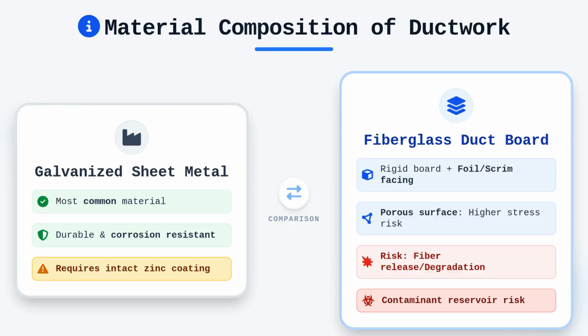Galvanized sheet metal remains the most common material due to its durability and resistance to corrosion, provided the zinc coating remains intact. However, you will frequently encounter fiberglass ductboard, which presents a far more complex challenge. This material consists of a rigid insulation board with a factory-applied foil or scrim facing on the interior. Because this surface is porous, it behaves differently under mechanical stress compared to smooth metal surfaces. When you apply agitation to fiberglass, you must remain acutely aware of the potential for material degradation or fiber release. If the integrity of the surface is compromised, the ductboard may become a reservoir for contaminants rather than a passive conveyance surface.